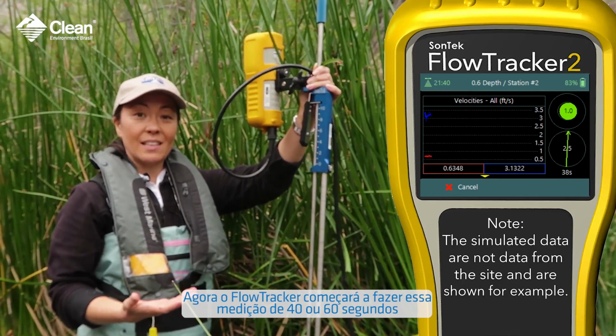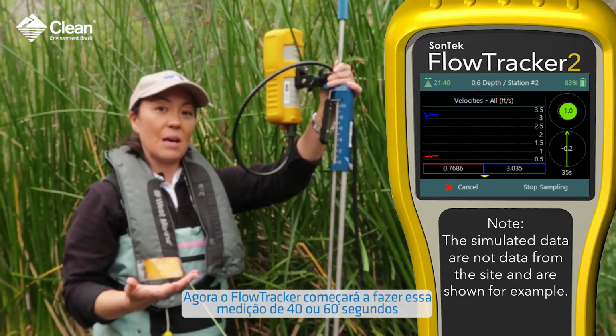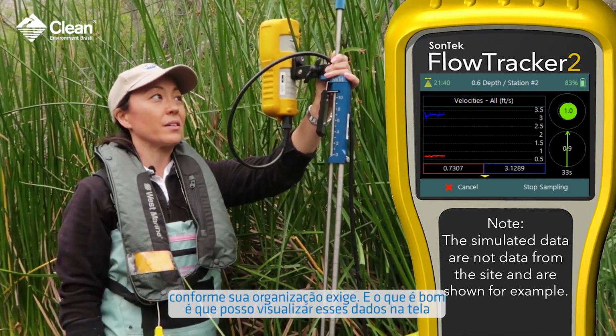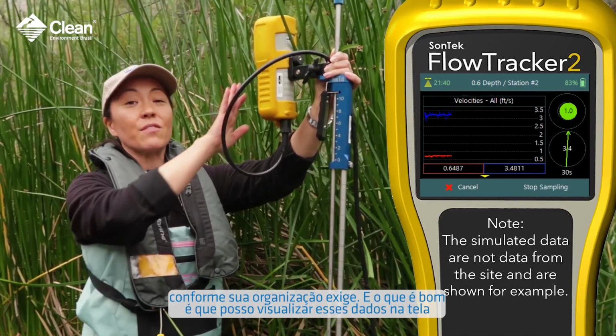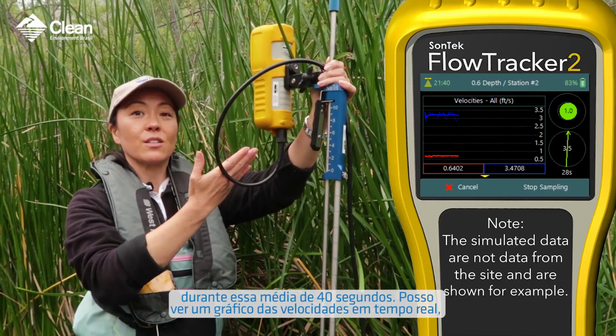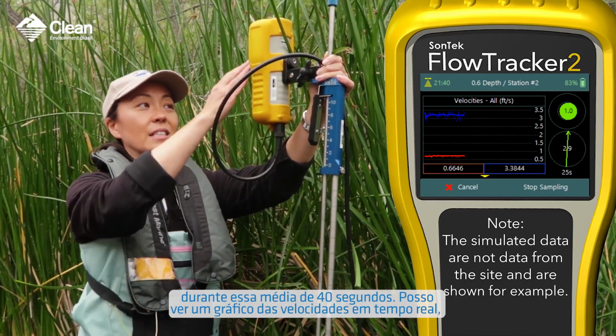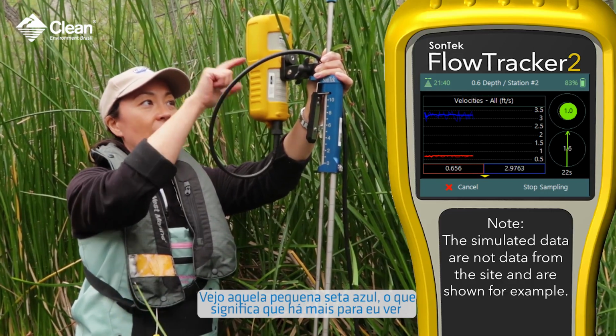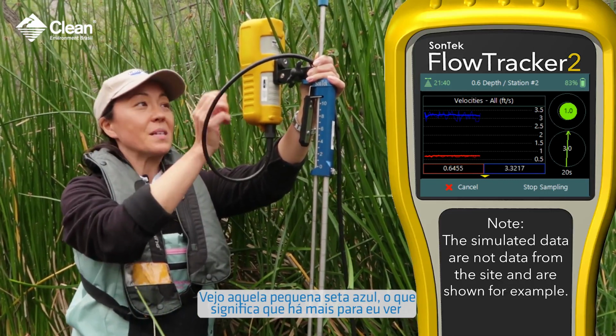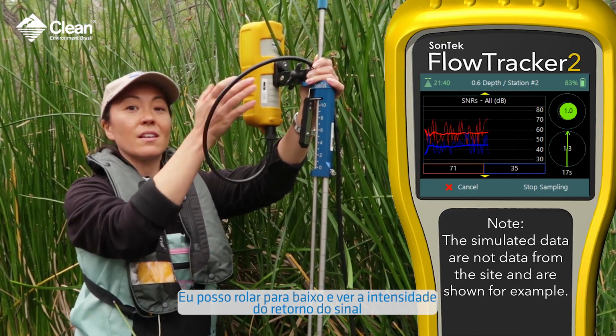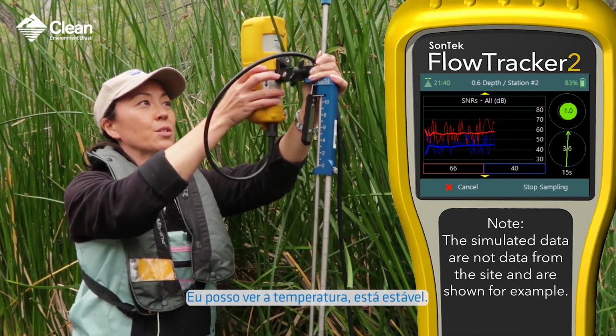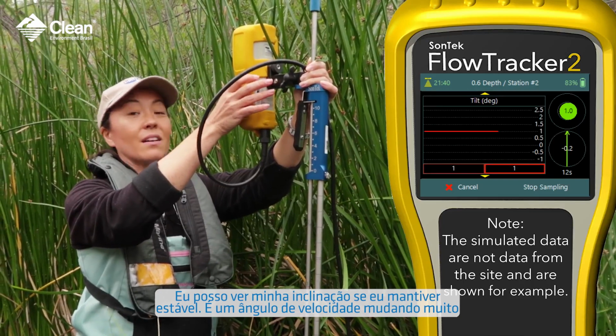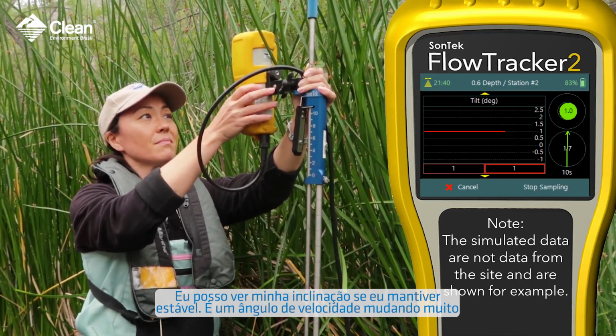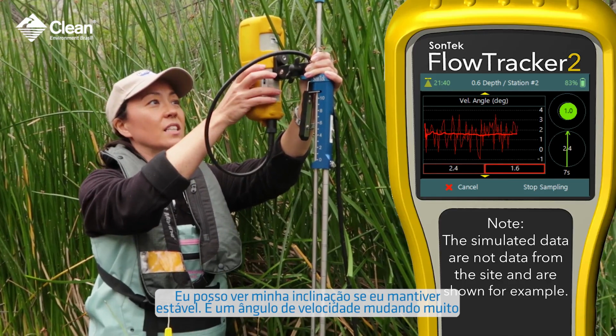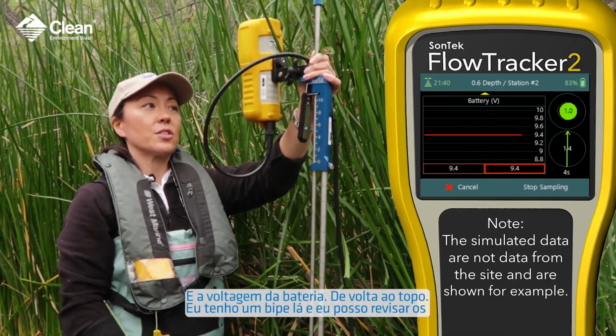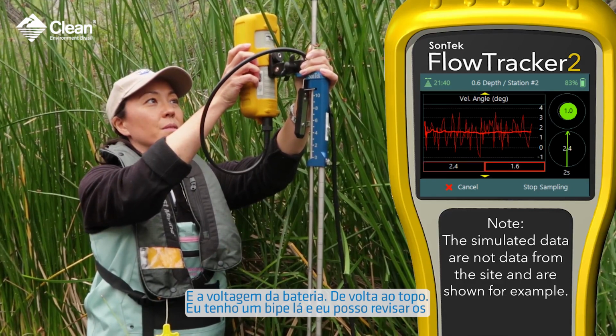Now the FlowTracker will begin taking that 40-second or 60-second measurement as your organization requires. And what's nice is that I can view those data on the screen during this 40-second average. I can see a plot of the velocities in real time. I see that little blue arrow, so that means there's more for me to see. I can scroll down and see the SNRs, the signal strength. I can see the temperature, is it steady? I can see my tilt if I held it steady. Is the velocity angle shifting a lot? And battery voltage. Or back up to the top.